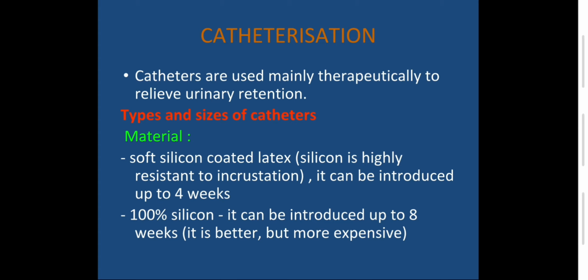Most commonly we use silicone material or soft silicone-coated latex. Silicone is highly resistant to incrustation. It is an inert material, more comfortable to the patient with less irritation and less infection. It can be indwelled up to 4 weeks. The 100% pure silicone catheter can be indwelled for up to 8 weeks. It's better, but it is more expensive.